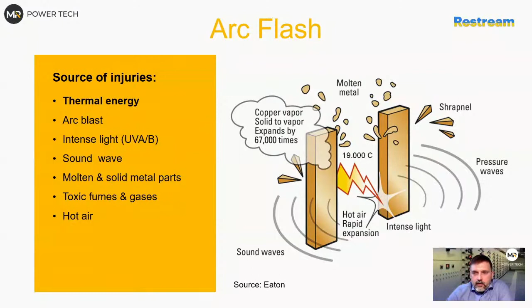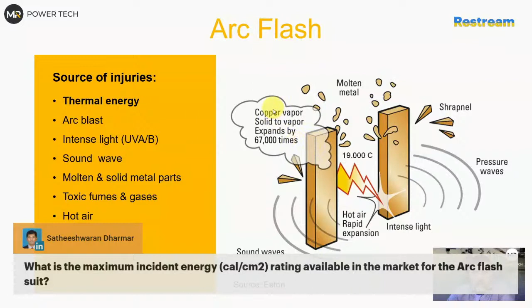But what is the maximum incident energy in calories per square centimeter rating available in the market for the arc flash suit? So as far as I know, and this will be kind of commercial now, because I have provided for customers of mine on some projects, the highest one is 140 calories per square centimeter. And this is something that Oberon does in the US. And in Europe, as far as I know, we have up to 100 calories per square centimeter. So this is at least for the suit, the maximum rating I'm aware of. And typically you find a lot of things up to 40 calories. But if you would like to go above, it's not that easy to find.